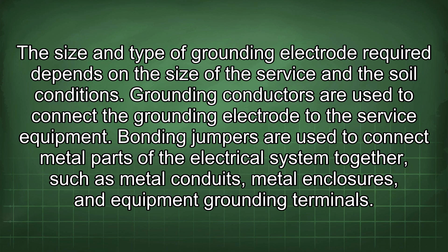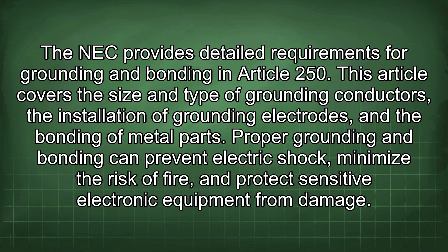The NEC provides detailed requirements for grounding and bonding in Article 250. This article covers the size and type of grounding conductors, the installation of grounding electrodes, and the bonding of metal parts. Proper grounding and bonding can prevent electric shock, minimize the risk of fire, and protect sensitive electronic equipment from damage.